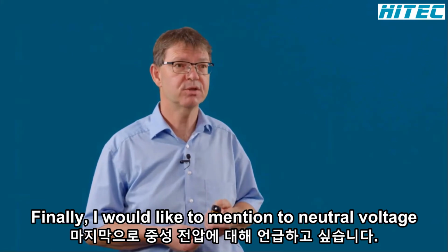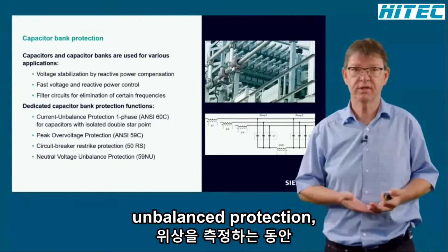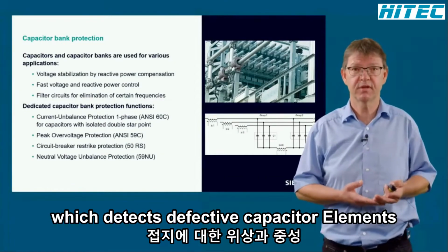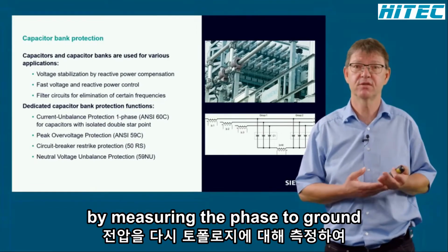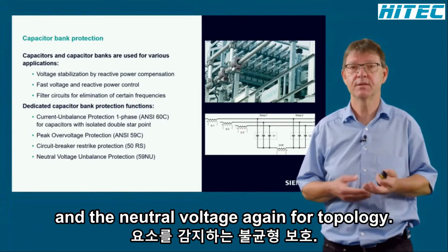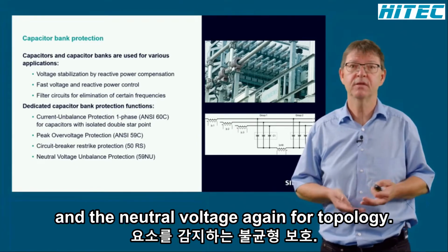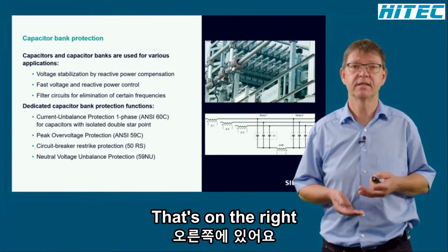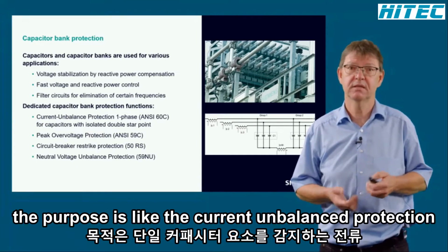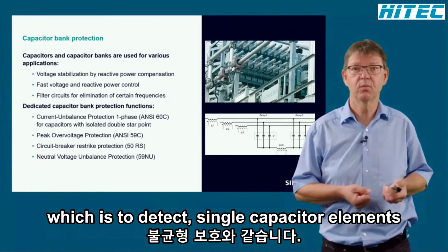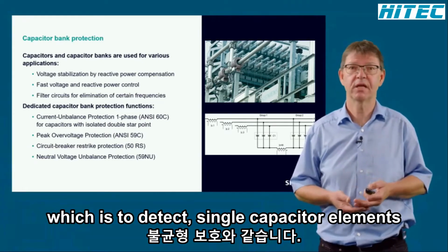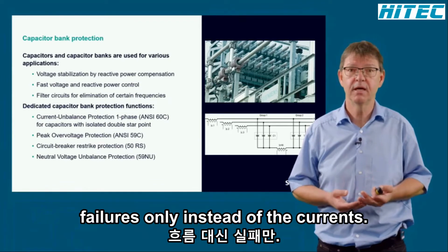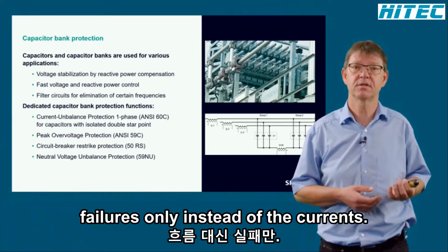Finally, I would like to mention the neutral voltage unbalance protection, which detects defective capacitor elements by measuring the phase to ground voltages and the neutral voltage. Again, for topology, as on the right-hand side. The purpose is like the current unbalance protection, which is to detect single capacitor element failures only, that voltages instead of the currents are used.